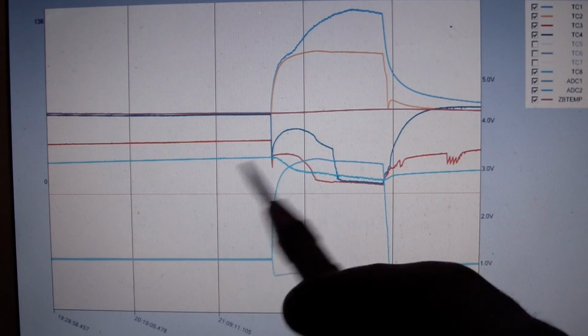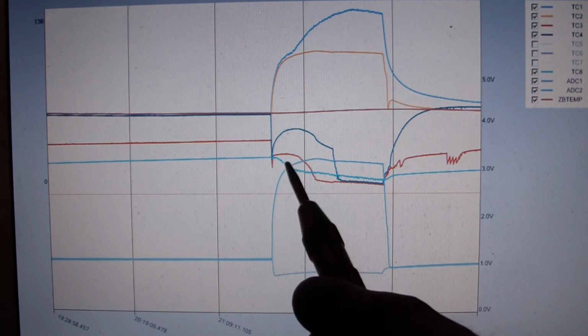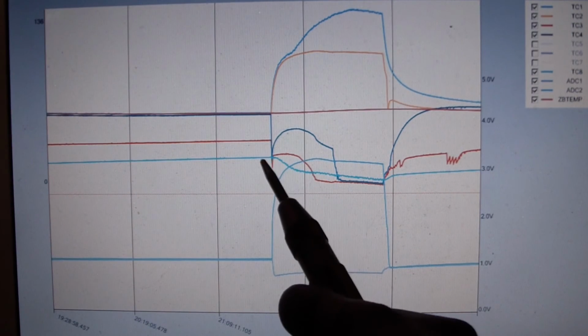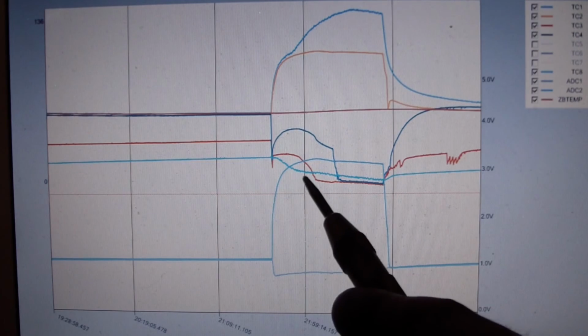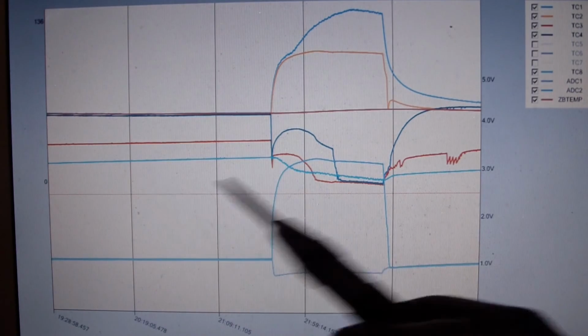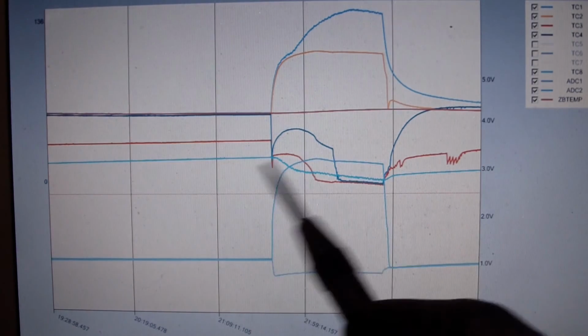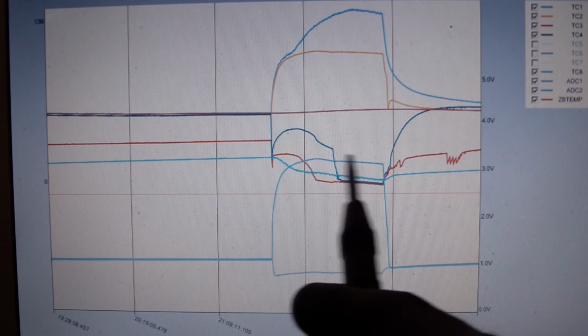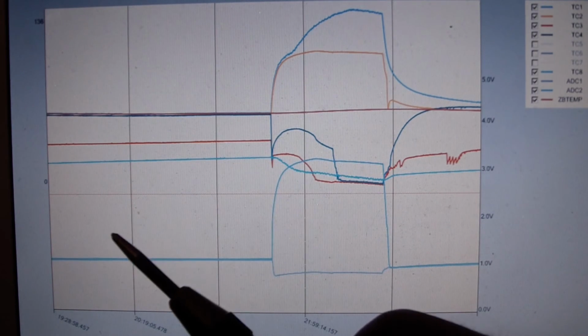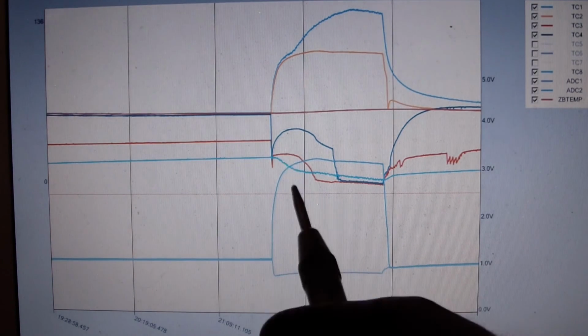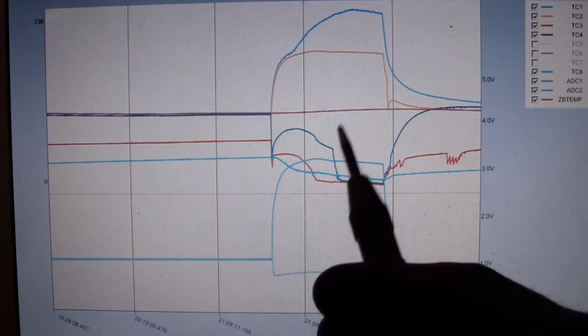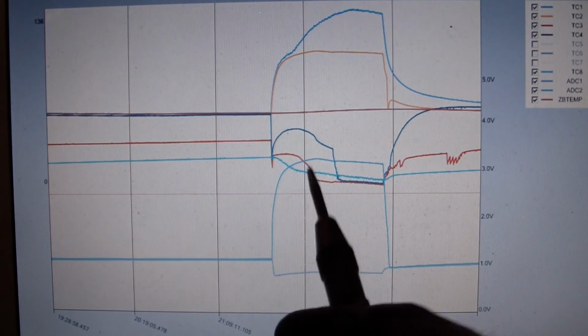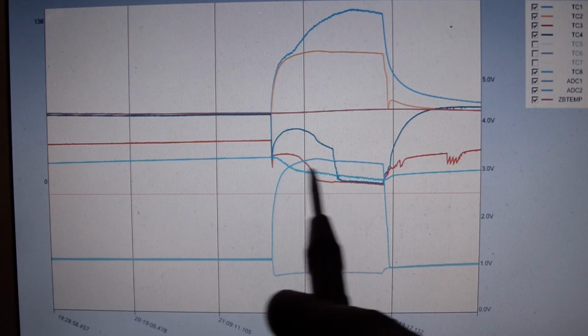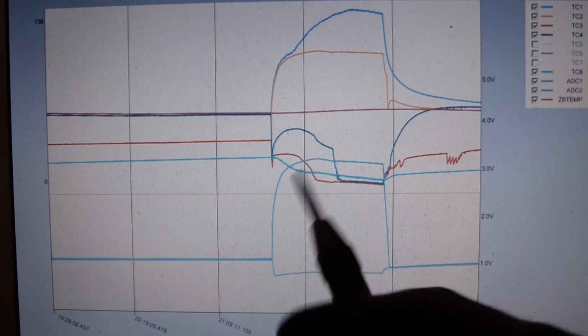I'd like to experiment with removing that heat interchanger, or at least removing maybe 2/3 of it and going down to about 1 foot of capillary tubing, just to provide myself a little bit of protection against slugging back to the compressor, and see how it overall affects the performance here. That's probably one of the first things I'm going to do. Actually, one of the first things I'm going to do is add a little more refrigerant and see how that affects the shape and length of time that this horn exists in.